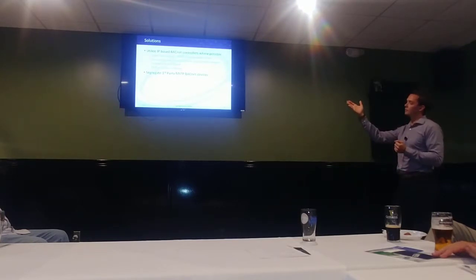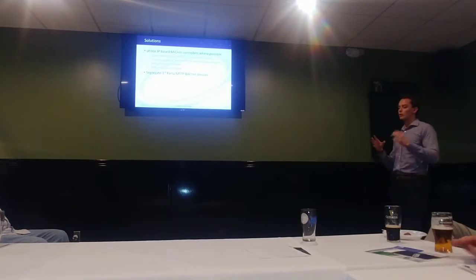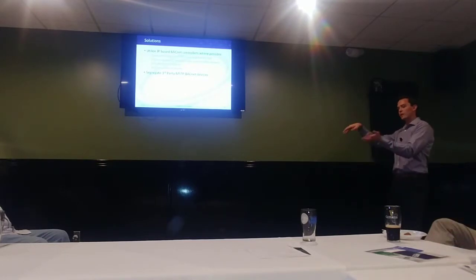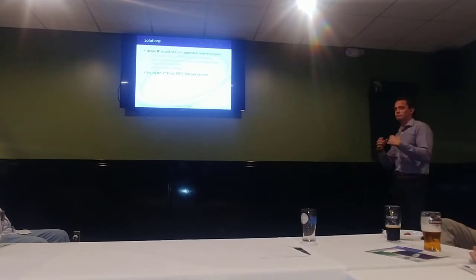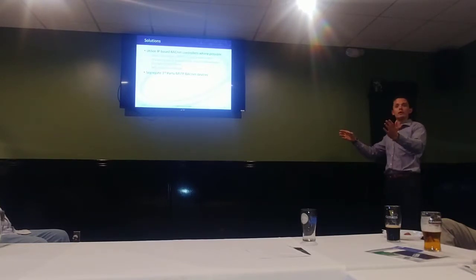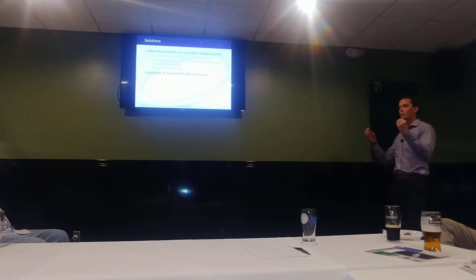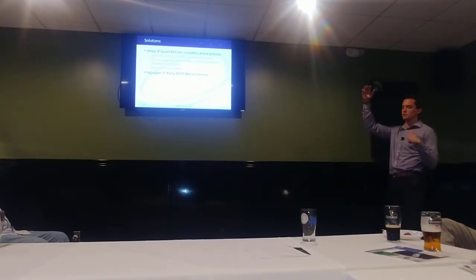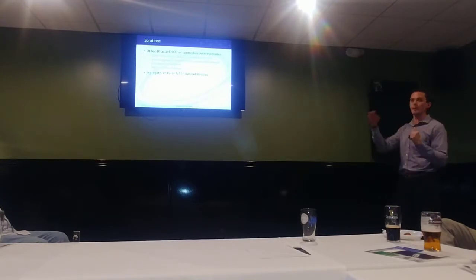Another suggestion, or another solution we had, was segregating third-party BACnet devices. We would try to take third-party devices, VFDs, chillers, boilers, those types of things, and segregate them on a different segment of our network than we had our Delta devices on. Not that they're not good devices or not perfectly fine BACnet, but sometimes a manufacturer will have 200 variables or 200 points on a chiller, and we found that mixing those with our MSTP networks would sometimes slow it down or communicate at a different baud rate. In order to maintain that integrity all the way up to the SCADA side, we segregated those on their own MSTP loop.